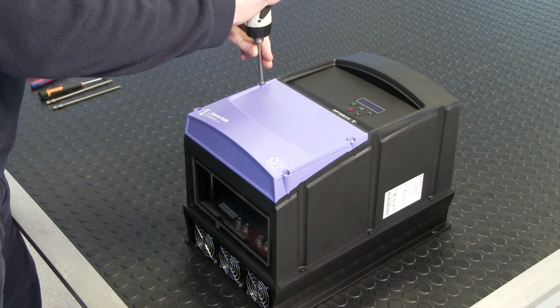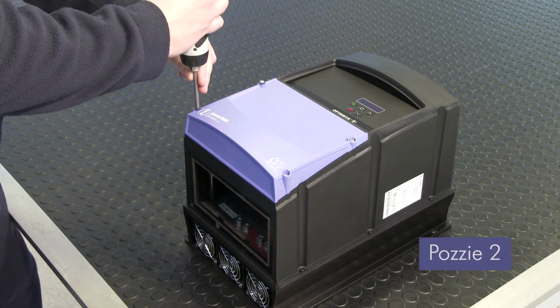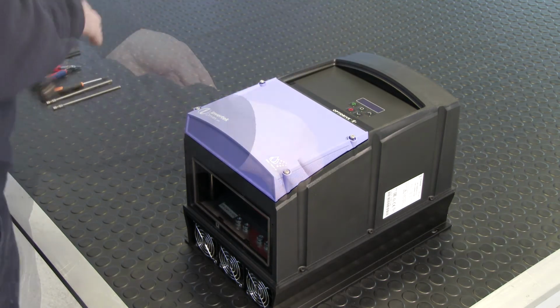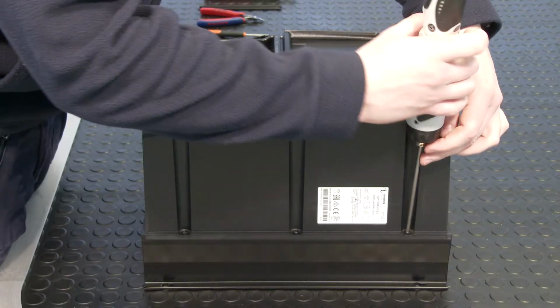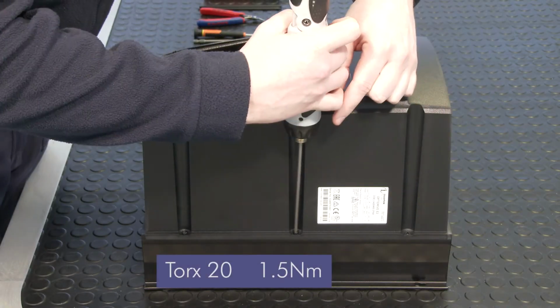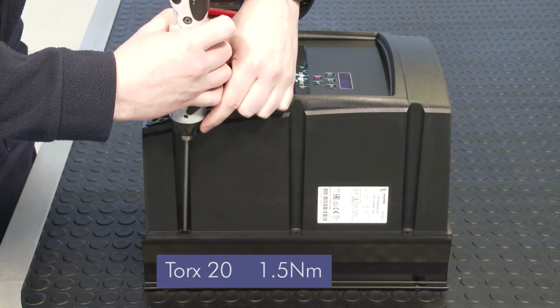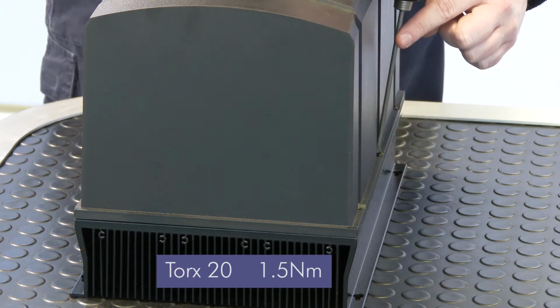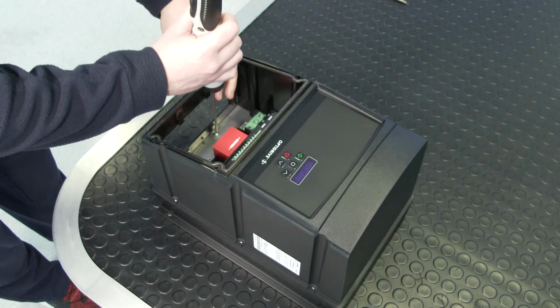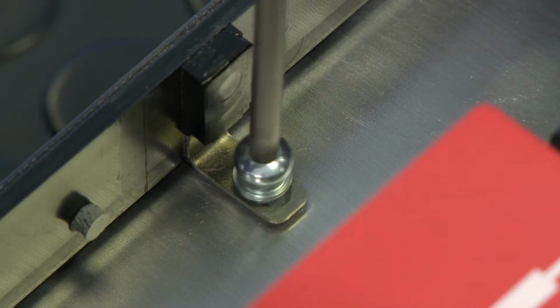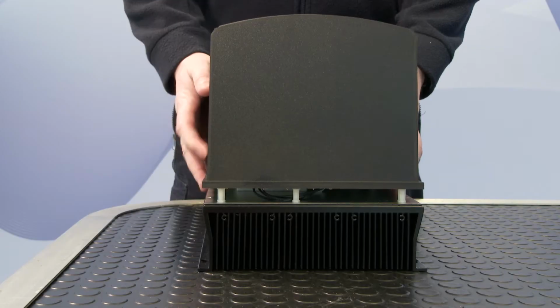To remove the control cover, use a POSI 2 screwdriver to loosen the 4 screws and lift the cover away. Using a Torx 20 screwdriver, remove the 6 cover screws and earth tab screw. The torque setting is 1.5 Nm. The cover can now be lifted away from the heatsink.